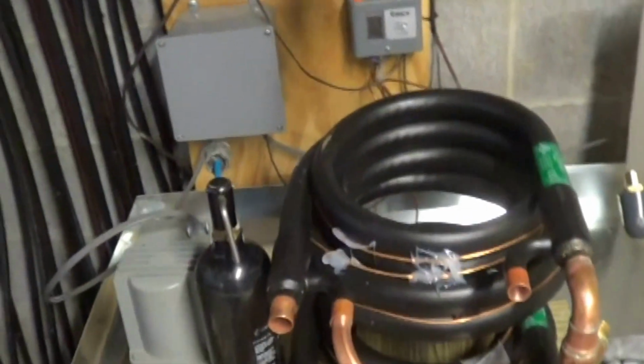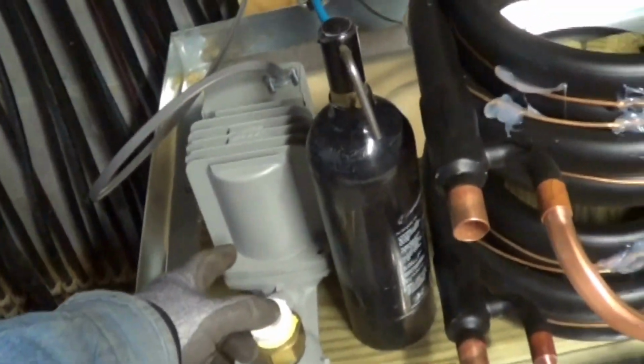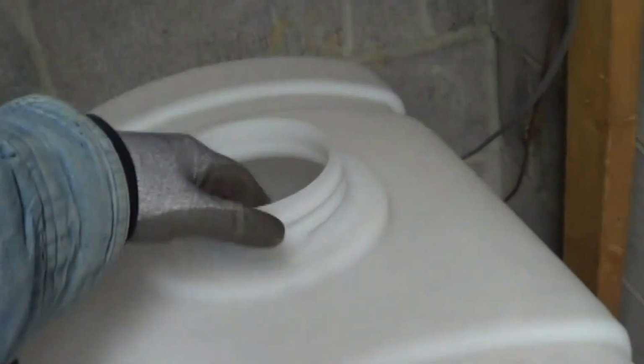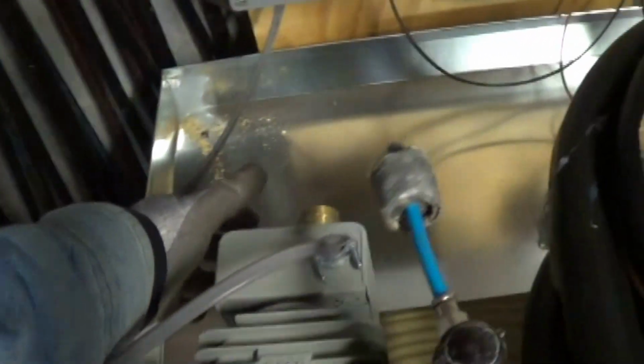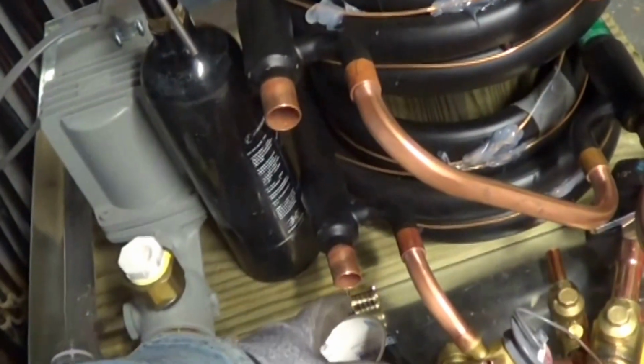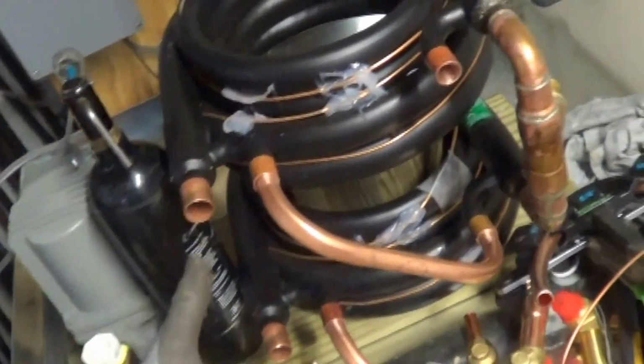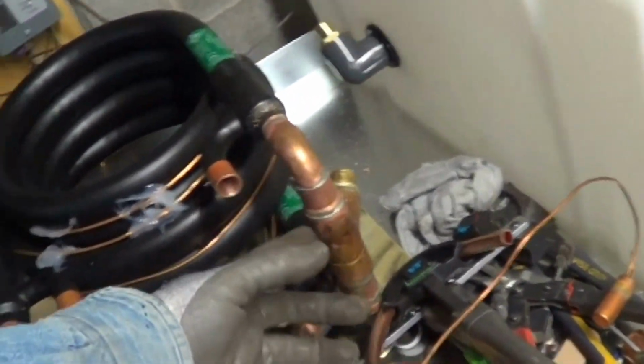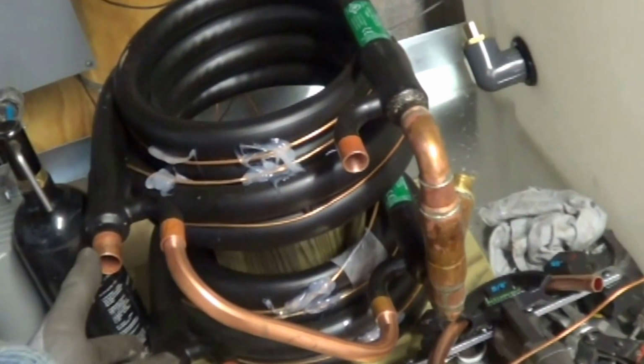Using PEX for the water connections, 1 inch, and pretty simple. Draw water off the bottom of the tank, go straight into the pump. I'll have a strainer inside the tank. This tank's kind of nice, I can reach my arm in there. Get a strainer, then out of the pump, just zoom around here to the heat exchanger. And the heat exchanger, I got them piped in parallel on the water. That way I want to have maximum water flow.